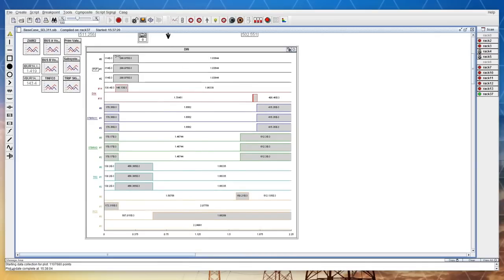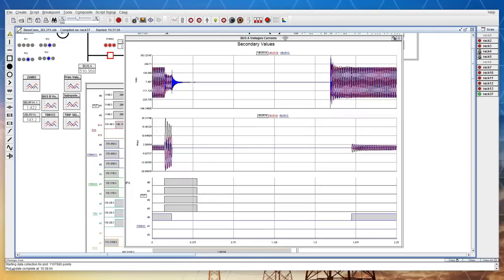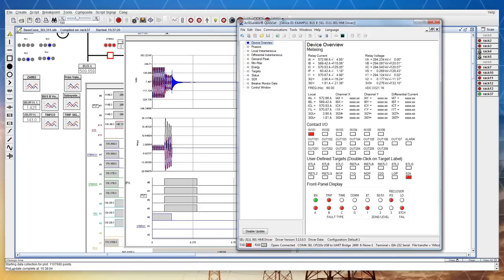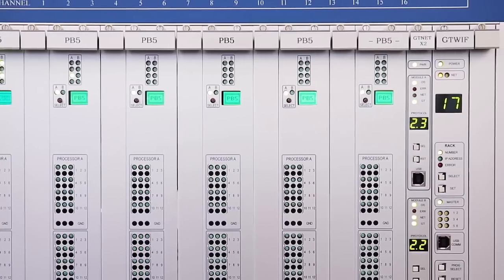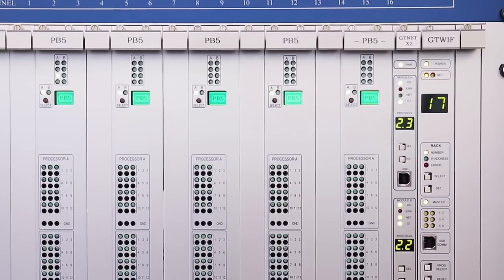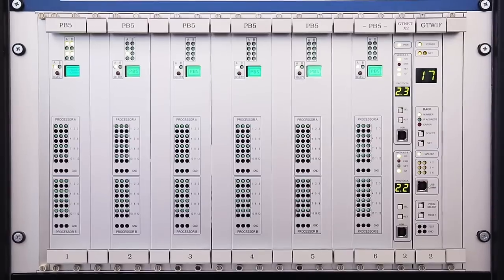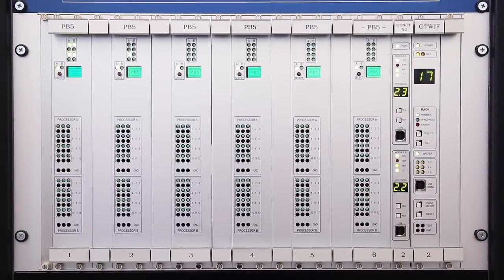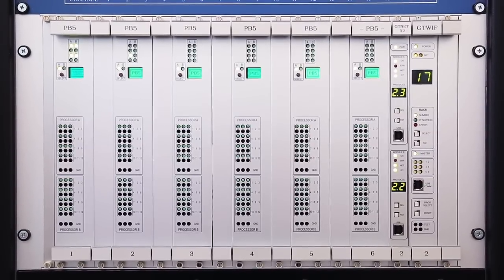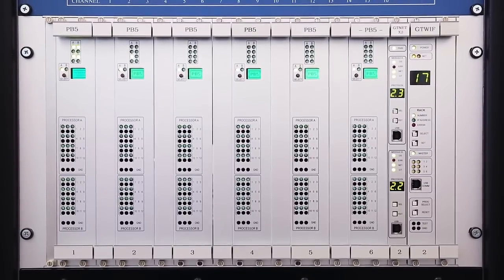Protection testing with the RTDS simulator can also be conducted using an IEC-61850 interface. The RTDS simulator's GT-Net-X2 network interface card allows the simulator to communicate with the physical relay using LAN-based protocols.